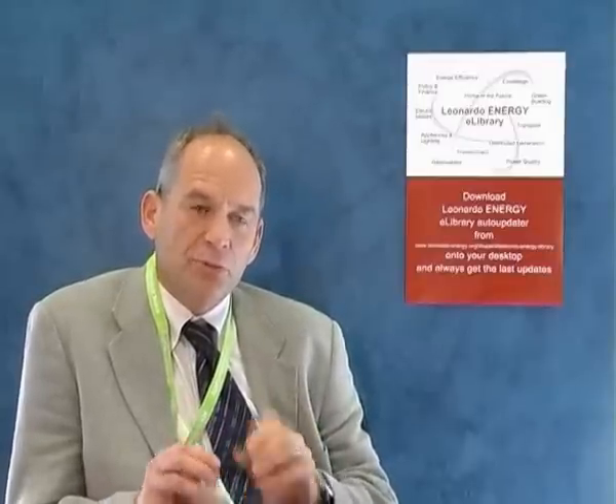So what we presented here in Barcelona is how you can achieve these requirements for the point of connection, and the flicker requirement is one important start. We have to look at the impedance of the grid, we have to look at the voltage, because the voltage and the impedance of the grid is, I think, the responsibility of the grid operator. And when we look at a customer, it's the current that is the responsibility of the customer. Starting with flicker, we have defined these harmonics of the voltages and this grid impedance.